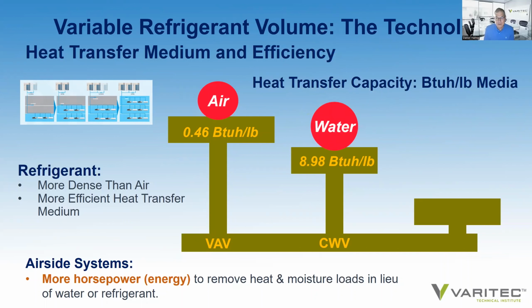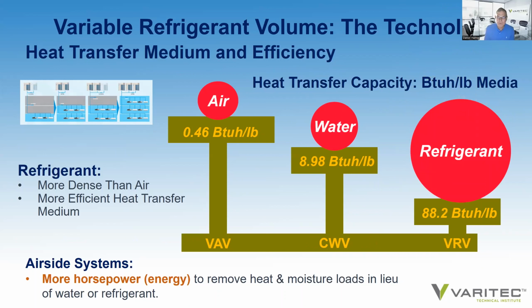I've been an advocate of chill beam systems for years. And the reason why chill beam systems are energy efficient is because water is the heat transfer medium for a building's sensible load. Water is a denser heat transfer medium, and it can hold 8.98 BTUs of energy per pound of water. So you need a lot less water to move the same amount of energy than you do air. Consequently, you have less system horsepower. Well, let's look at refrigerant. Refrigerant is an even more dense heat transfer medium. Refrigerant can hold 88.2 BTUs per pound of refrigerant. Consequently, you can move an awful lot more energy with a lot less refrigerant than you can with either water or air. So these systems invite every consideration as an energy efficient heat transfer solution.